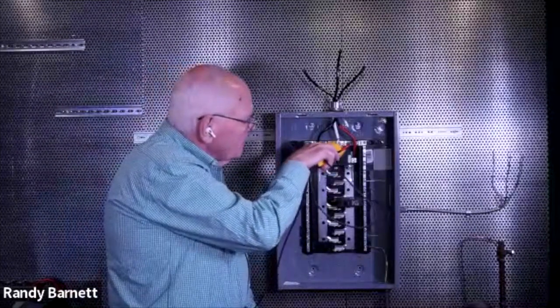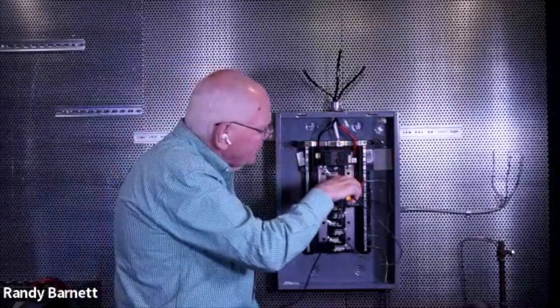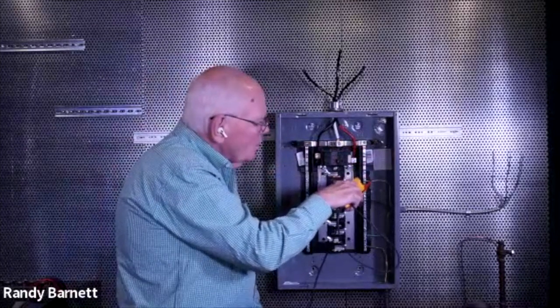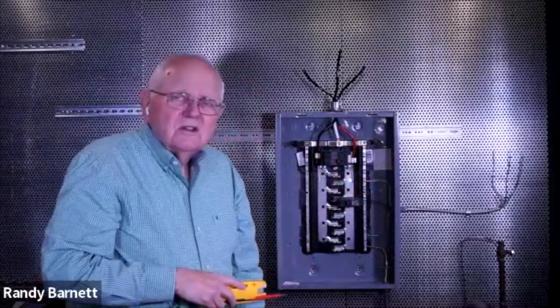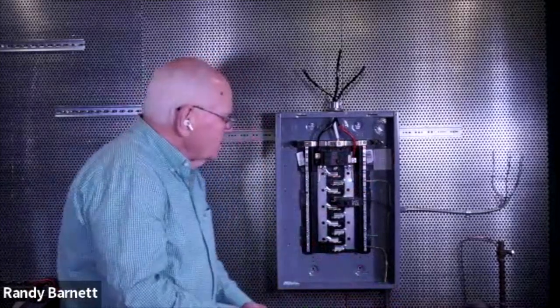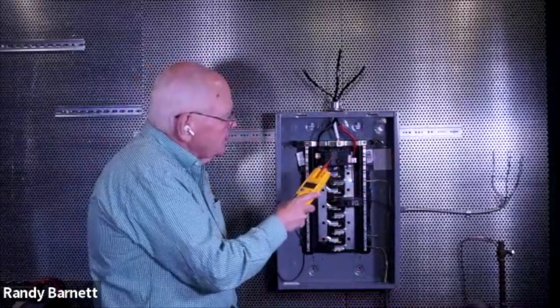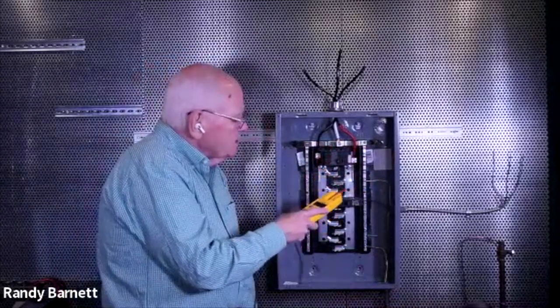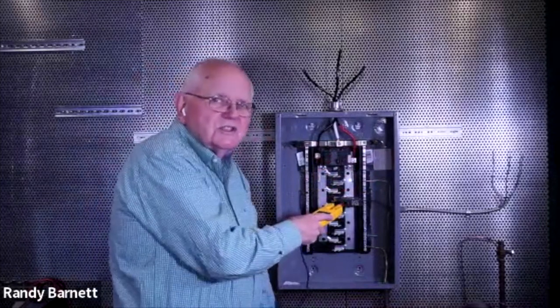So there's a bus bar that runs along behind the red wire and comes down here on the right-hand side, and there's a white wire connected to it. Well, that would also be a neutral conductor or a grounded conductor. The ungrounded conductors, of course, feed through the main circuit breaker into the bus bars. And so my ungrounded conductor would be attached to the circuit breaker.